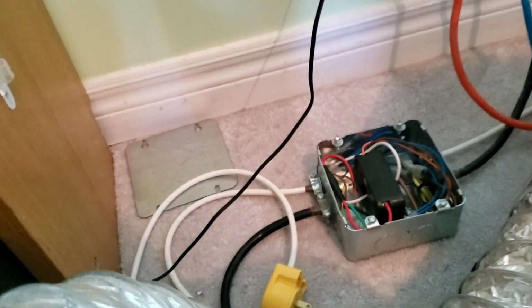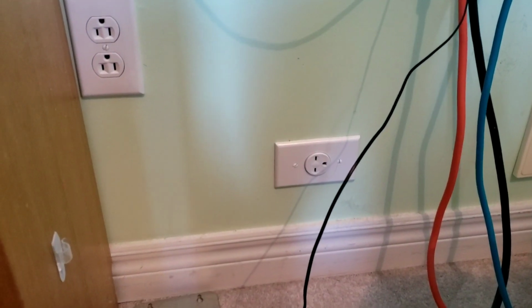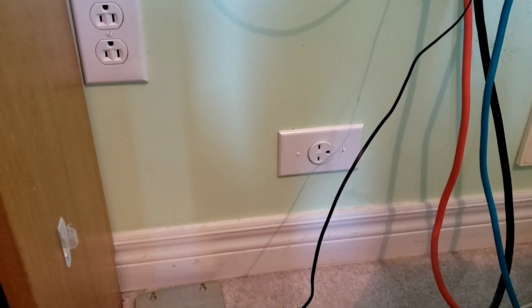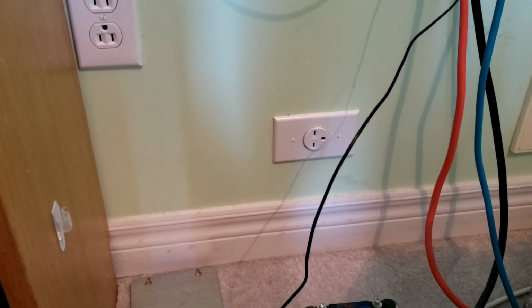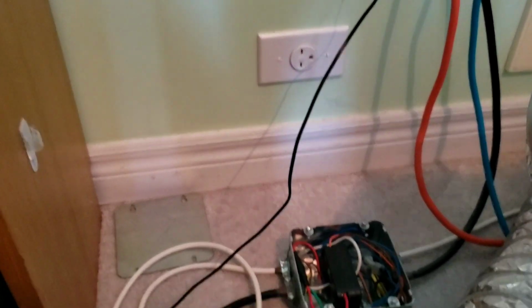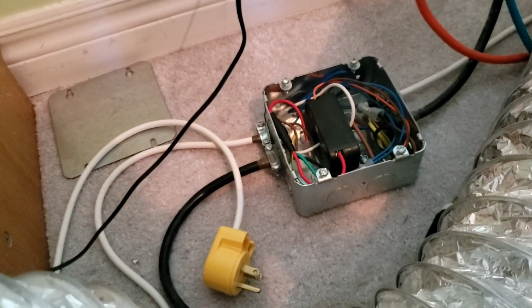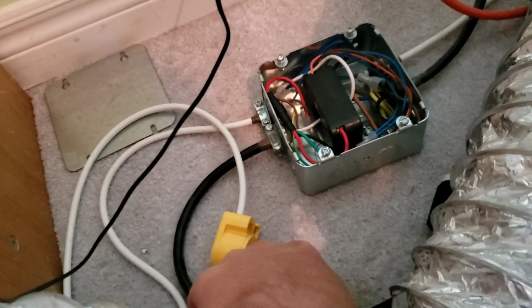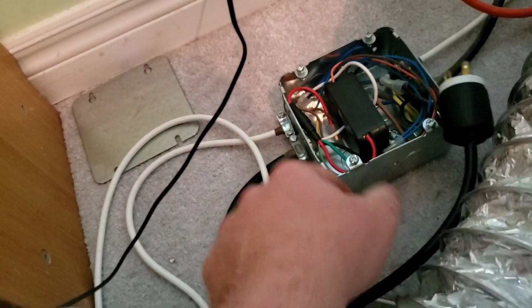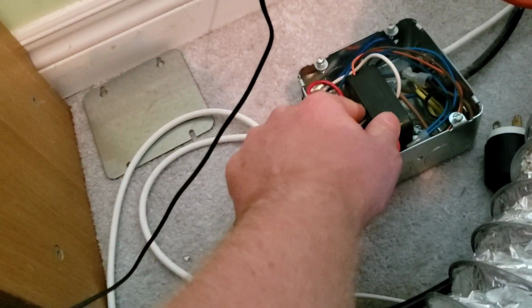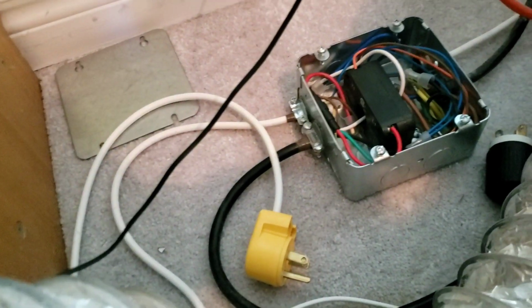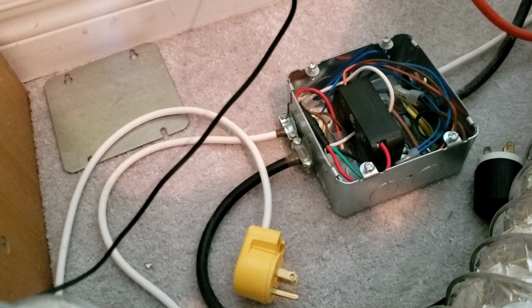So about 1 amp total, so I just plug it into my standard receptacle wired up with my other receptacles, like with my 2 bedrooms, 12 receptacles max by code. And this one's wire goes through that current switch, acting kind of like a primary winding, just one loop going through it, and these wires are my switch contacts that turn on the booster fan.